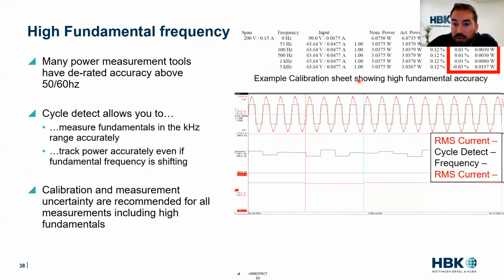If we look at an example of our calibration sheet, we actually offer calibration up to 5 kilohertz with every card, because we realize our customers are going through a wide variety of frequencies. Our measurement uncertainty is extremely good at those high fundamentals compared to the marketplace. So cycle detect is really key for being very accurate at the high fundamental. If you have a high pole count motor or a high phase count motor, there's a very good chance you are going to a high fundamental and need to consider your accuracy on electrical power.